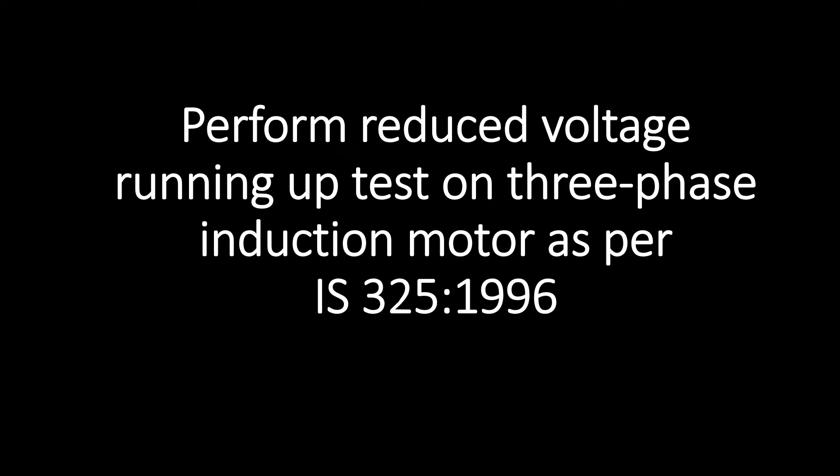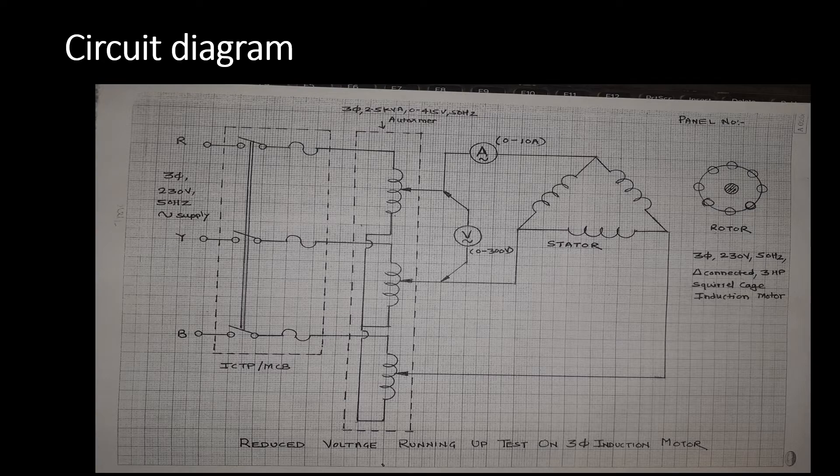Perform reduced voltage running up test on 3-phase induction motor as per IS 325 1996. Reduced voltage running up test is a routine test which is carried out on 3-phase induction motor. To carry out this test, make the connections as per this circuit diagram.